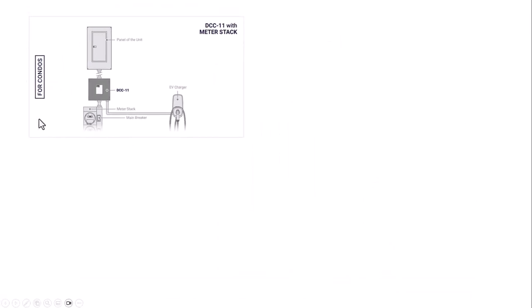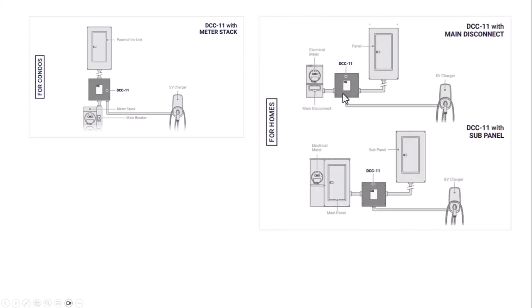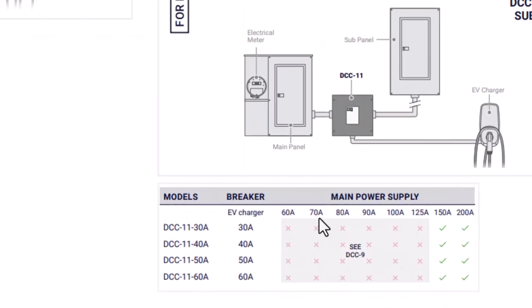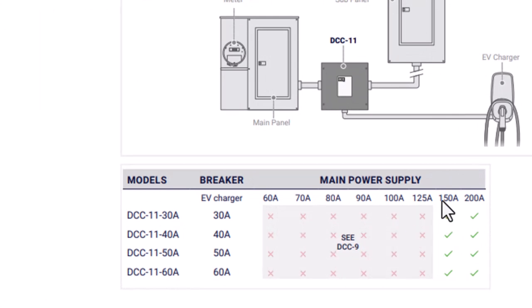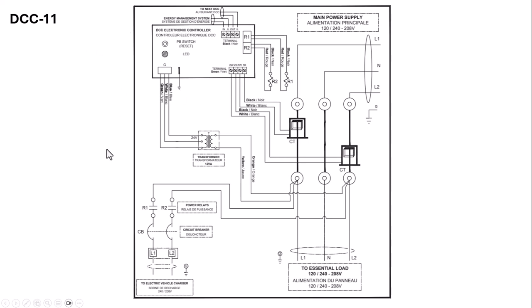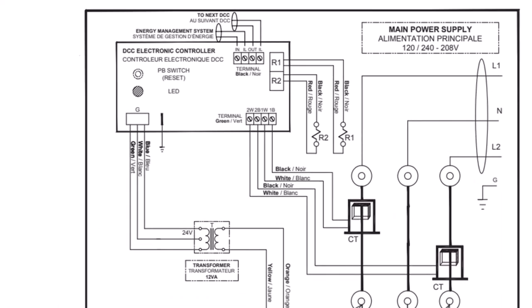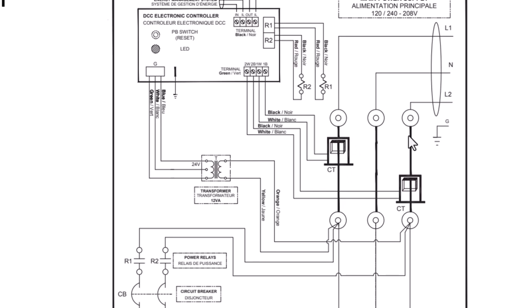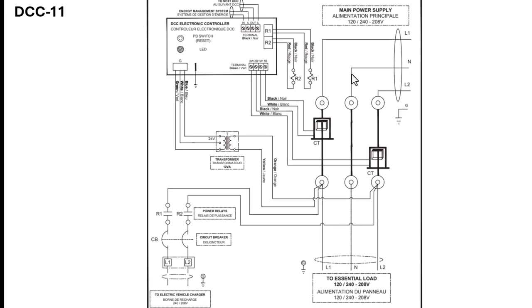So the DCC-11 again looks like this. We just covered it. It's very similar to the DCC-9, except that the amperage for this is higher than the DCC-9. And again, it's very similar installation. It's in series to the main feeder right here into the panel. And the rating is higher than the 9. It goes 150 amps to 200 amps, and the DCC-9 is 125 and down, as listed here. So the DCC-11, here's another wiring diagram showing the internal components. So basically the line, this is your main power source. So you have 120 volt through here, through the CT, the other 120 volt through this CT, and then you have a neutral wire as well. And this all goes through to your normal load.